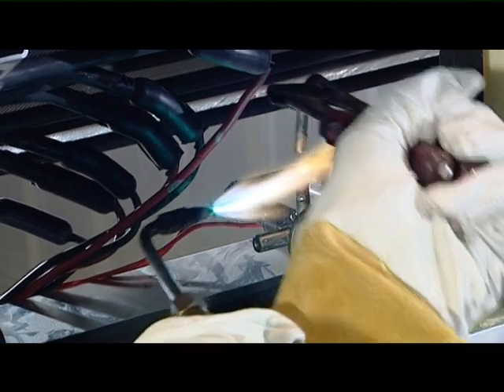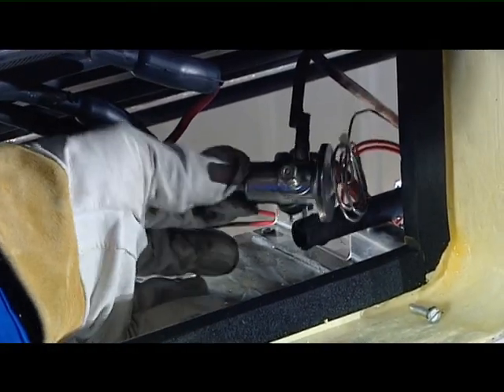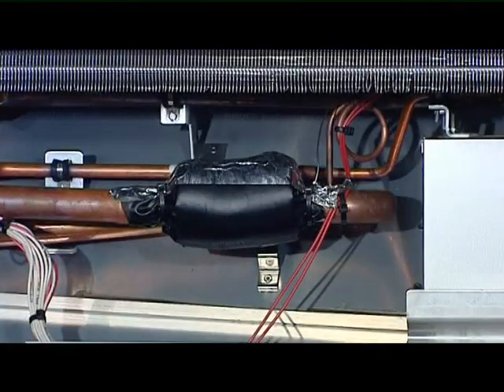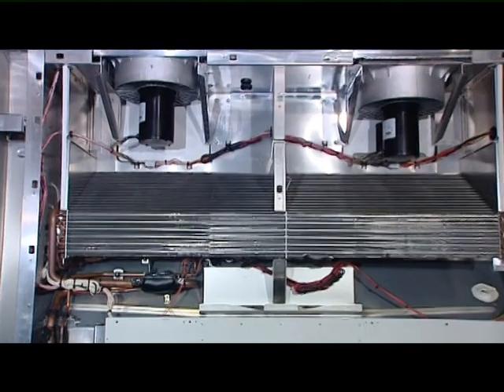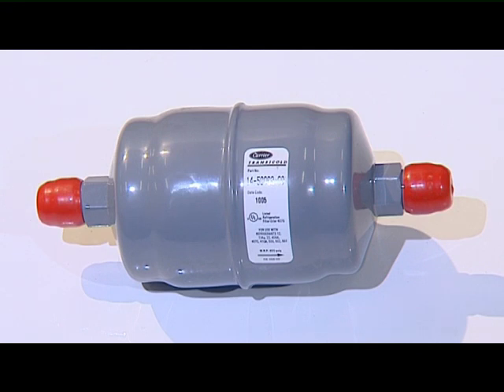Unbraze the valve's connections. Remove the valve and, in an emergency, simply cut the capillary tube. When fitting the new valve, place it as far as you can reach, but it is very important to fasten it securely and to insulate it. When replacing the TXV valve, always replace the filter dryer.